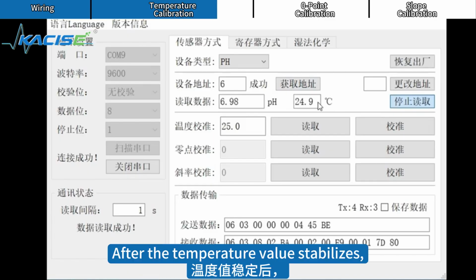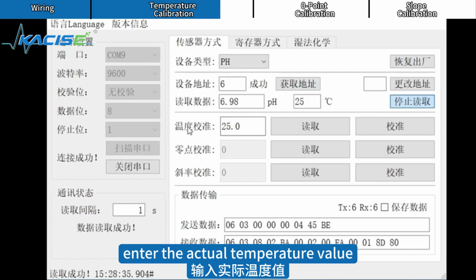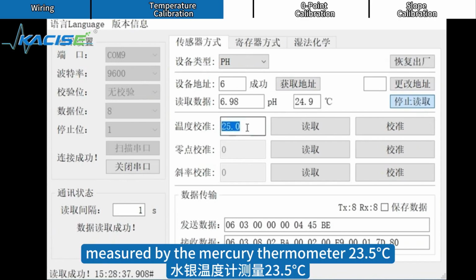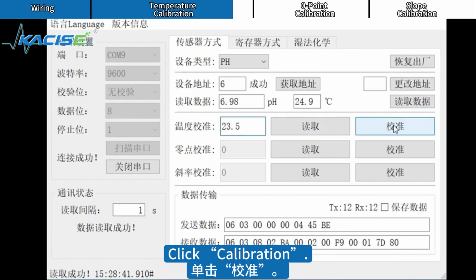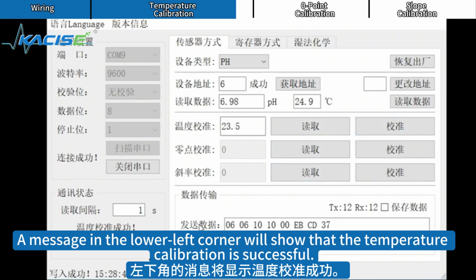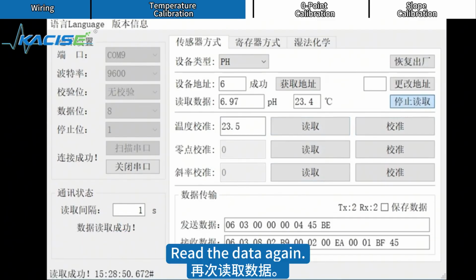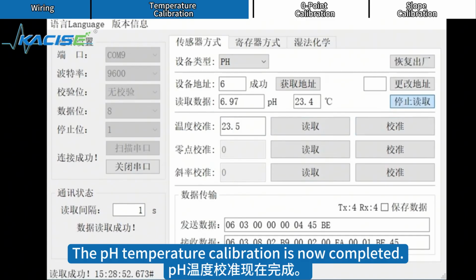After the temperature value stabilizes, enter the actual temperature value measured by the mercury thermometer, 23.5 degrees Celsius. Click Calibration. A message in the lower left corner will show that the temperature calibration is successful. Read the data again. The pH temperature calibration is now completed.